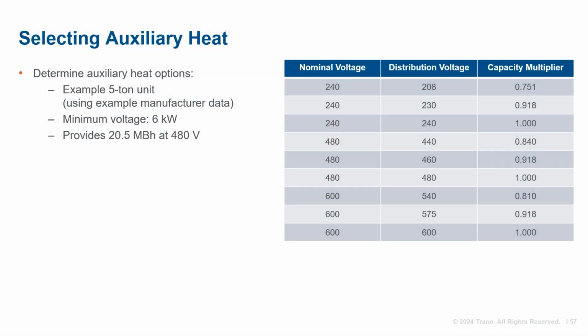For auxiliary heat sizing, you must pay attention to both the additional heat needed as well as the voltage of the heat pump unit. Varying voltage correction factors must be applied based on the job site electrical service. Taking into consideration the data from the previous slide, our example unit is a 460-volt unit, which requires an additional 14 MBH of heat based on our delta T calculation. Referring to the manufacturer's data, determine what auxiliary heat options are available and which best applies to our example system.